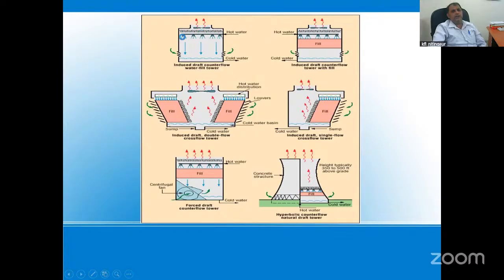Hot water enters the tower and is sprayed. Air enters from the side of the tower, and here is the induced draft fan. This fan induces the heat to the atmosphere. The second one is the fill. The fill area increases the surface area of the water droplets. When a drop contacts the fill zone area, it is splayed out, and as a result the surface area increases. This surface area increase leads to more and more heat transfer.